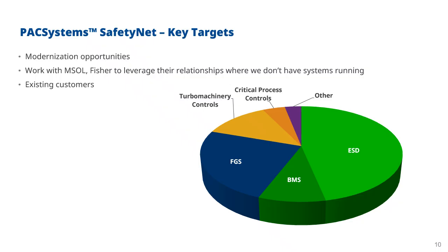One thing we're probably not getting involved in is turbo machinery and critical process controls. We just don't have the hardware for that. Turbo machinery needs some additional speed control and speed sensing, and critical process control is harder because unlike, say, a fire and gas or ESD system where the response times are quite slow, critical process control can need high-speed control instead.